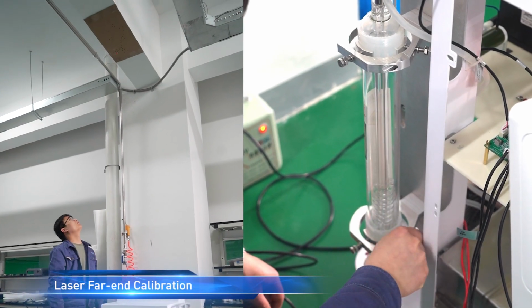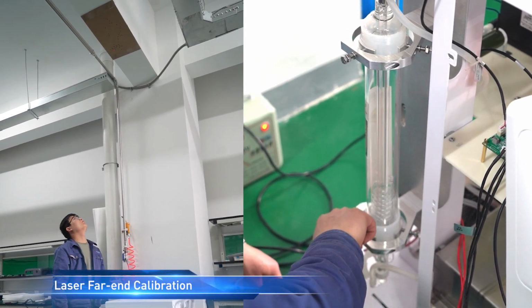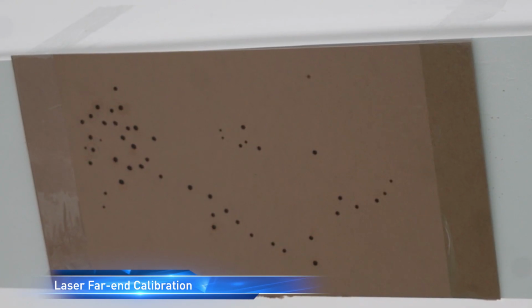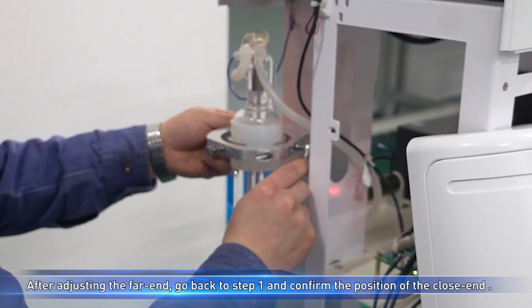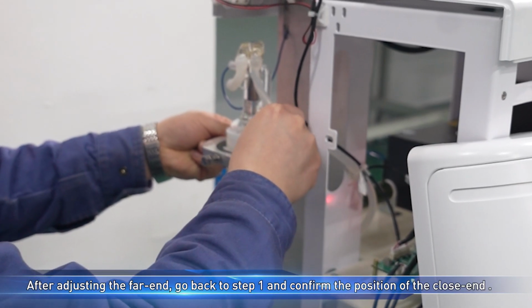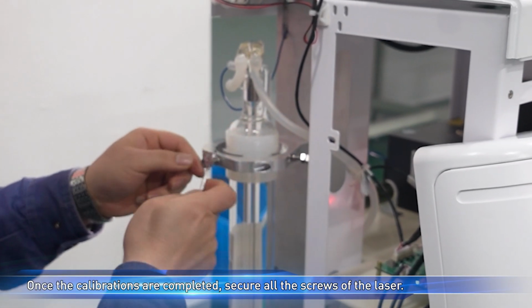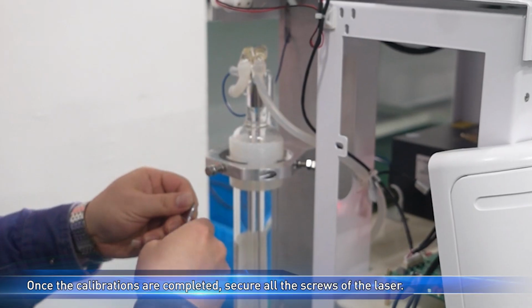Laser far end calibration. After adjusting the far end, go back to step 1 and confirm the position of the close end. Once the calibrations are completed, secure all the screws of the laser.